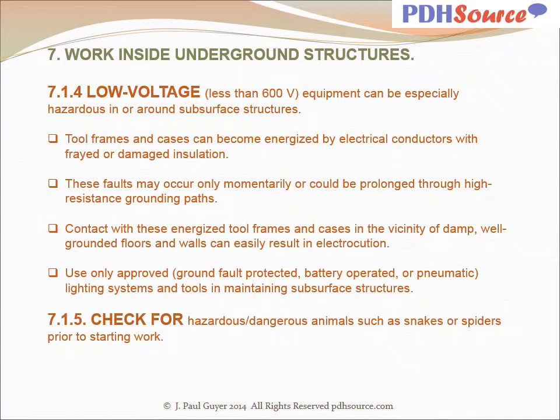For low voltage installations less than 600 volts, equipment can be especially hazardous in or around subsurface structures. Tool frames and cases can become energized by electrical conductors with frayed or damaged insulation. These faults may occur only momentarily or could be prolonged through high resistance grounding paths. Contact with these energized tool frames and cases in the vicinity of damp, well-grounded floors and walls can easily result in electrocution. Use only approved ground fault protected, battery operated, or pneumatic lighting systems and tools in maintaining subsurface structures. Check for hazardous and dangerous animals such as snakes or spiders prior to starting work.